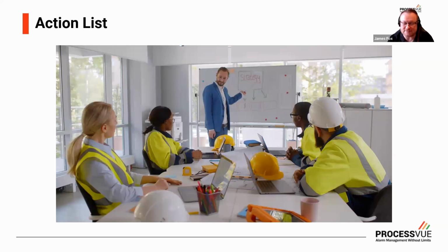Some may even get demoted to an event. There might be logic controls that need to be implemented in the host system, as we might be looking at and tackling nuisance alarms. We might be configuring some on delay timers to get rid of some chattering alarms, for example.